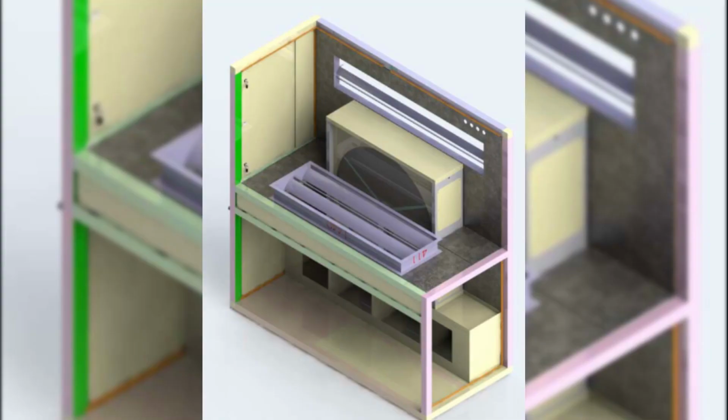6.2.4. Design requirements for HVAC systems in public assembly spaces for schools, including auditoriums, gymnasiums, and cafeterias. The requirements vary based on the type of project. New schools and major modernizations projects. 1. HVAC system. These projects must use custom single-zone variable air volume rooftop heat pump units or dual-temperature air handling units served by air-to-water chiller heaters.